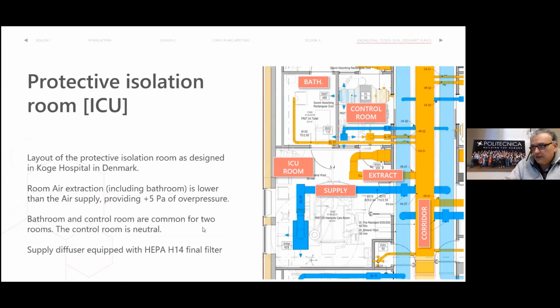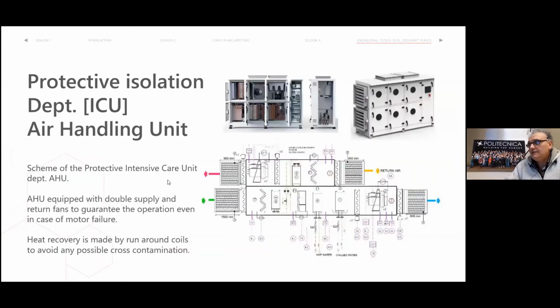Yes, here there is the HEPA H14 and it's okay. This is the unit that is provided for the protective isolation department. And even in this case, it shall be a dedicated unit. You cannot mix with other departments. You can make a unit which is modular type as usual, or you can also provide compact pre-assembled type.